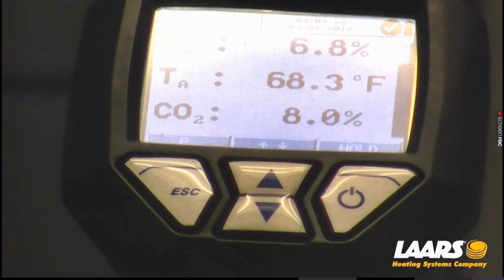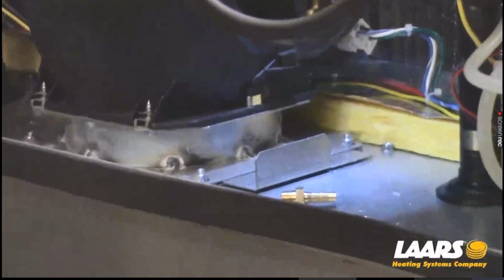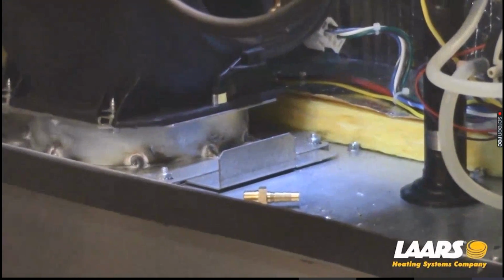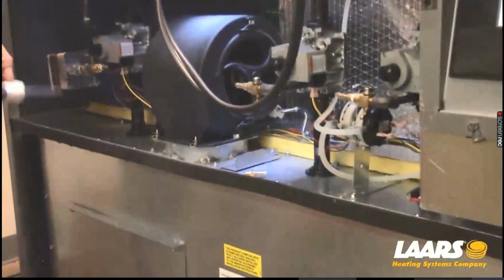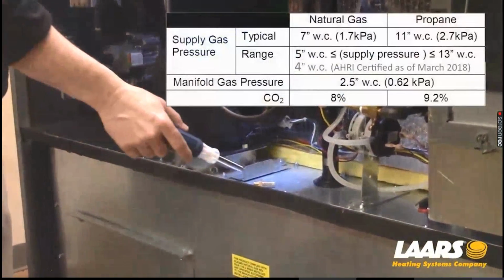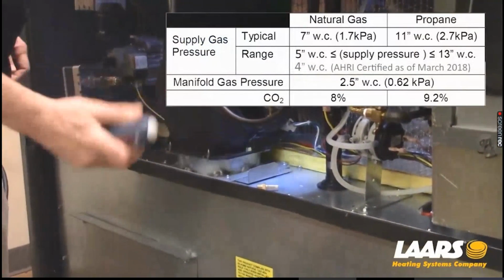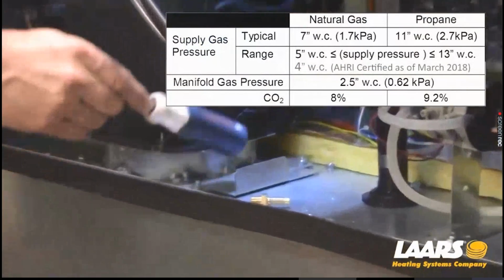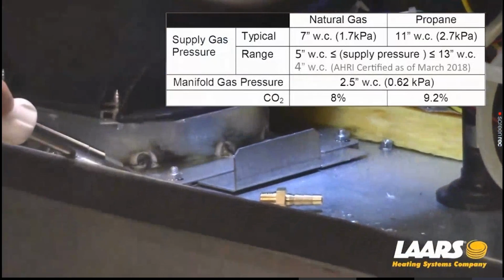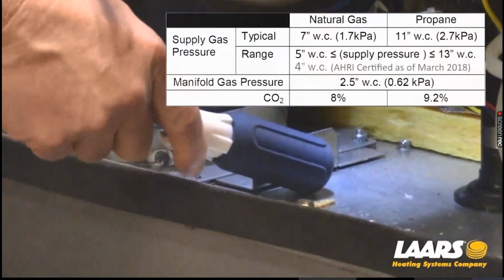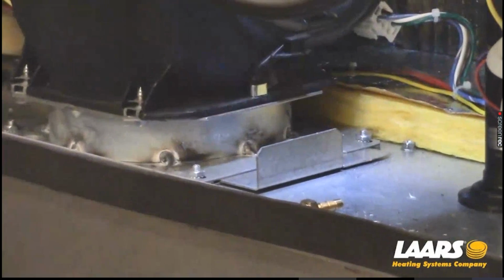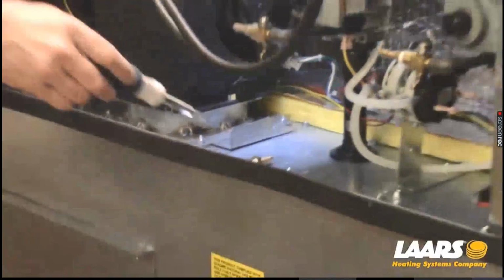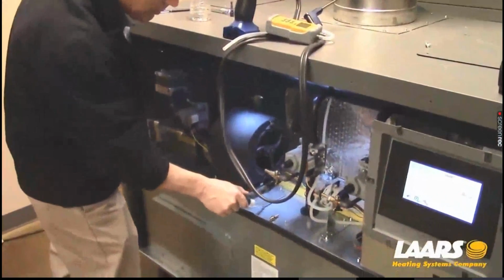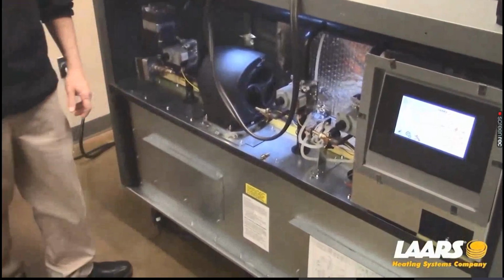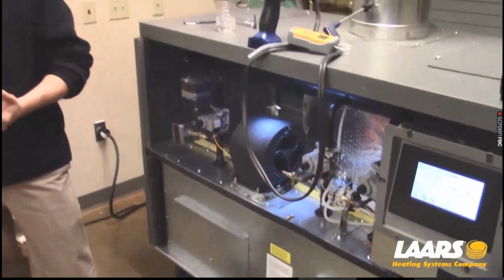Next is on that air shutter. If we have our gas valves all set at 2.5 inches of water column, it can be either natural or propane. It has to be at 2.5. This boiler I'm running natural gas, so my CO2 on natural gas is 8%. I can either open or close my air shutter, okay? You can loosen the nuts on the bottom part of the blower. However, you really just need to tap on it one way or the other to make your air shutter adjustment. When you're done, my suggestion, take a black magic marker and put a mark there. Now you know on the day you started it, your CO2s and manifold pressures were correct.